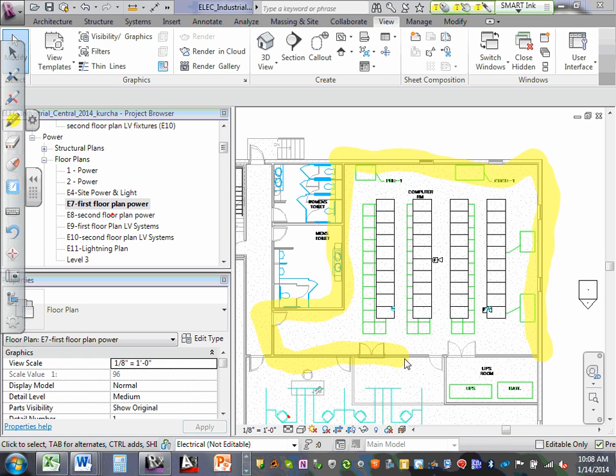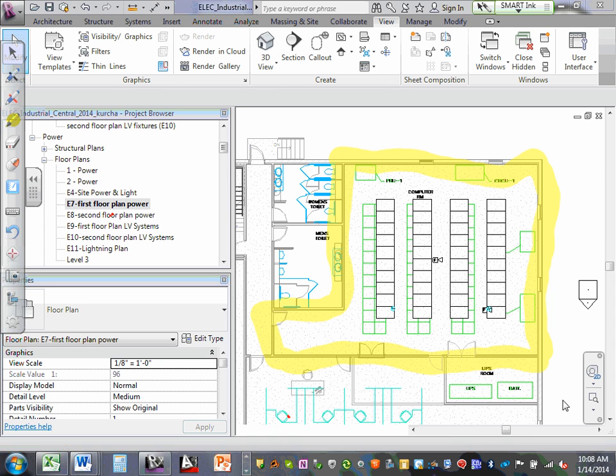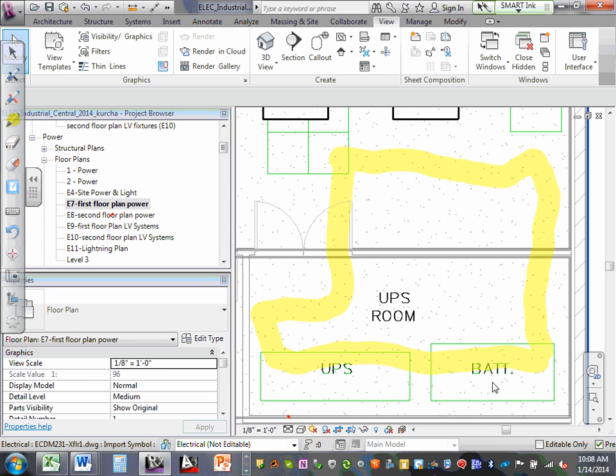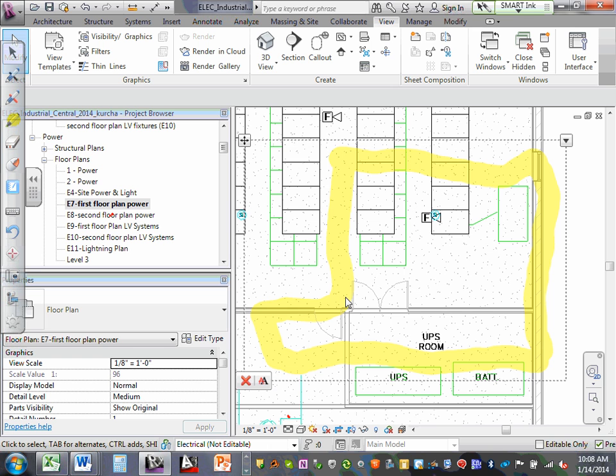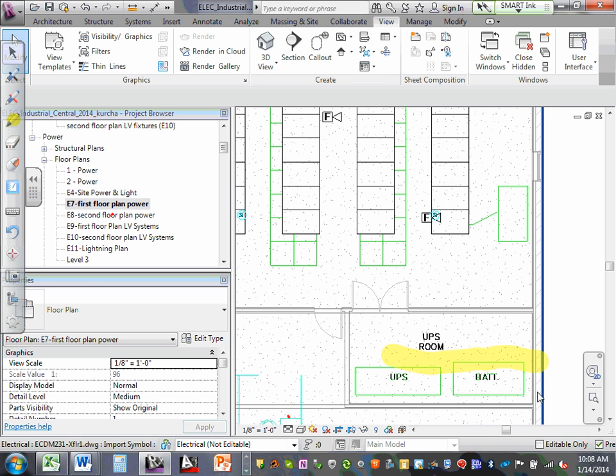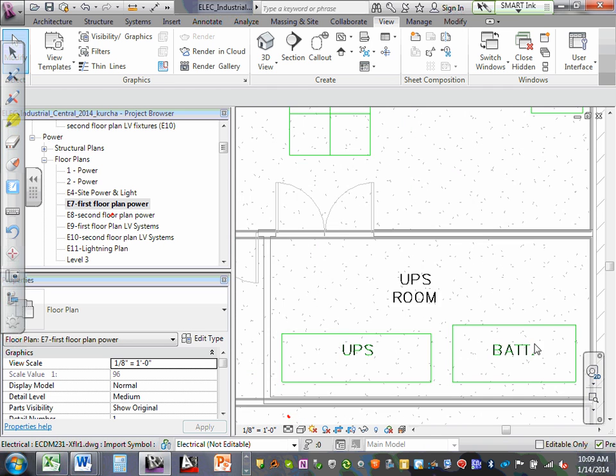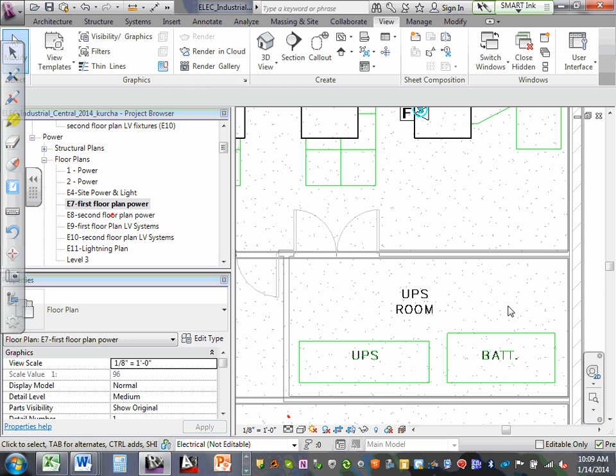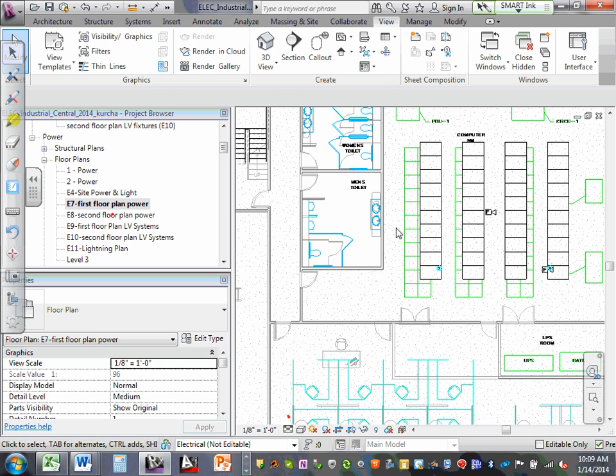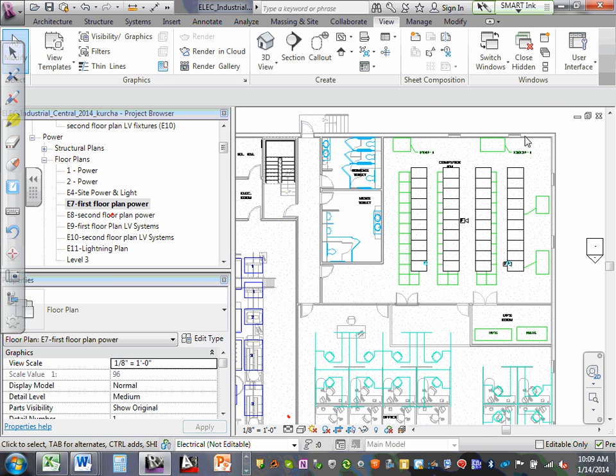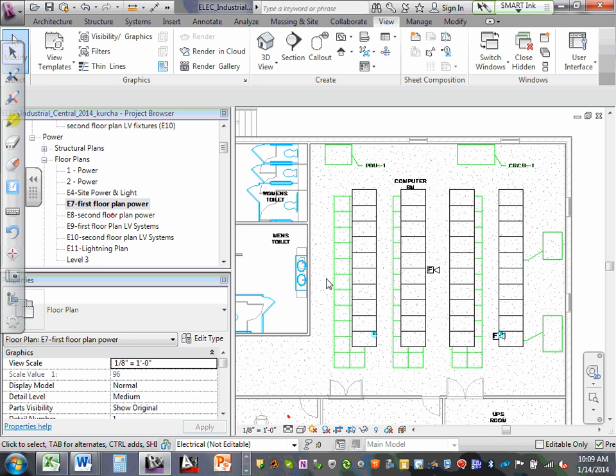Now the other thing that is not asked for, but UPS rooms are usually full of batteries. And batteries give off a gas. Anybody know what that gas is? Like acid. hydrogen. If I was designing this building as a consulting engineer, I would also include gas detection in that group as well. Because if batteries are going bad, they give off a lot more gas, which can become not only corrosive but also hazardous to human beings. So that's just a side note. So, standard placement of smoke detectors in the UPS room, and then cut your spacing in half in the computer room itself, both on the ceiling and in the subfloor.